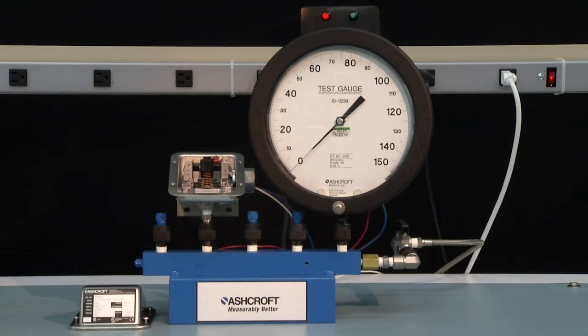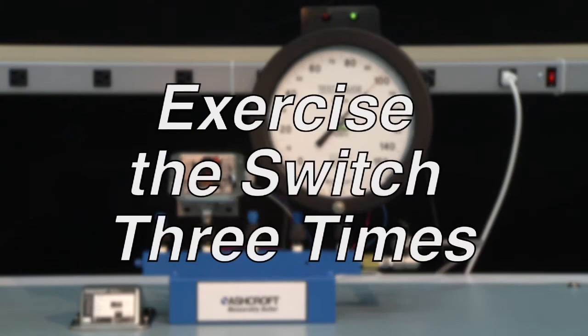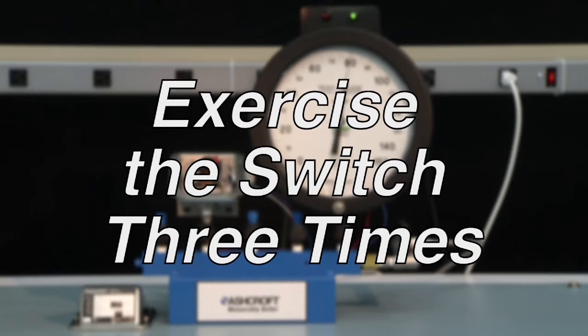The first step of calibration is to exercise the switch to make sure it is operating correctly. To exercise a switch, start from zero PSI and increase to full range of the switch. In this case 100 PSI and then return back to zero. This should be done three times.